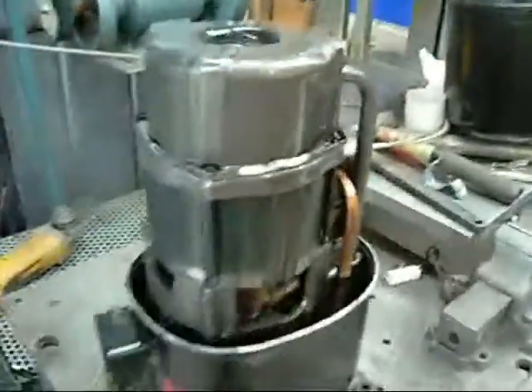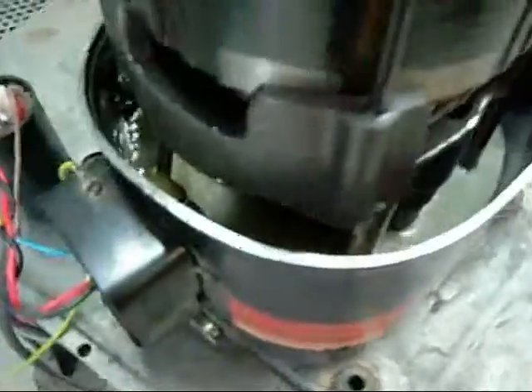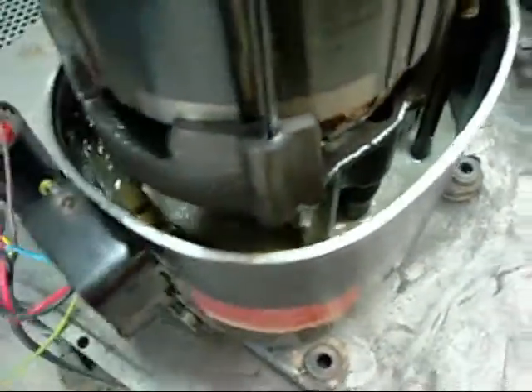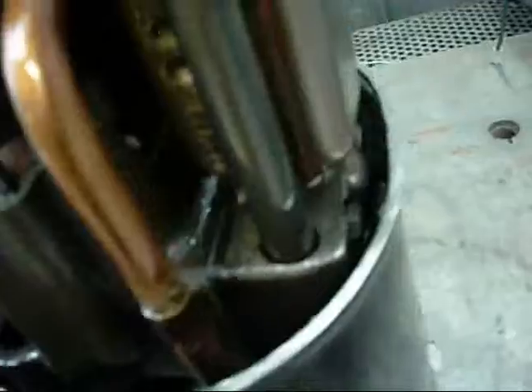Unfortunately this one's not going to work as a pump anymore, but I'll pull it apart and show you a bit more. And what is with the oil? It looks like there's still refrigerant dissolved into it — the more you stir it up, the more gas comes out. I'm guessing this one wasn't properly recovered either.